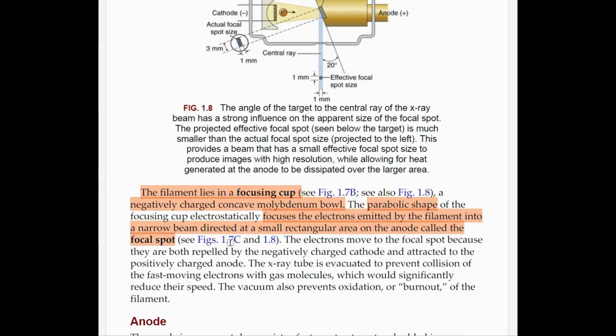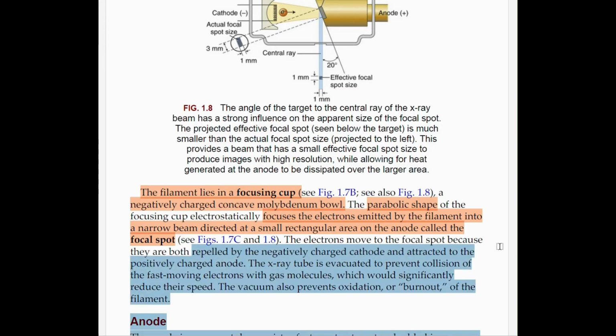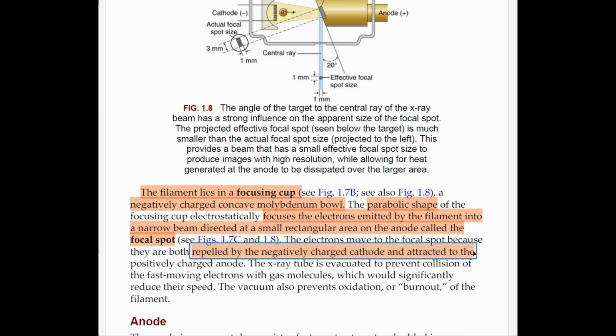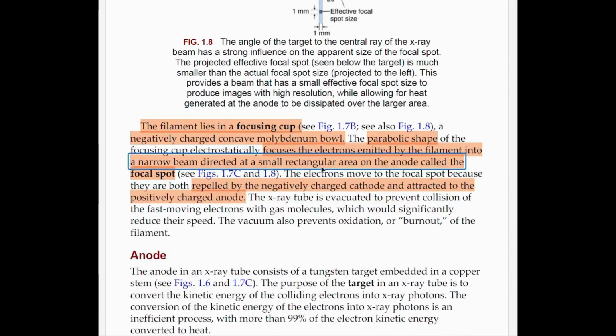and it directs those electron rays into a small rectangular area on the anode, which is called the focal spot. The electrons move to this focal spot because they are both repelled by the negatively charged cathode and attracted to the positively charged anode. That is the reason that the electrons move to the focal spot. Now we move on to the anode.